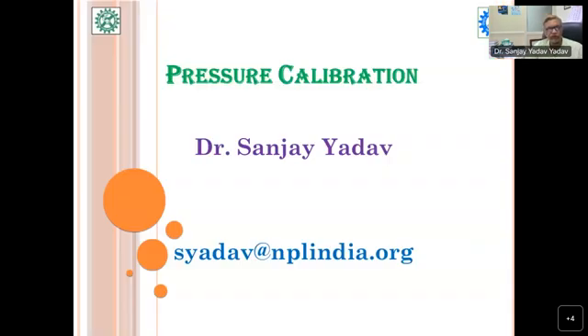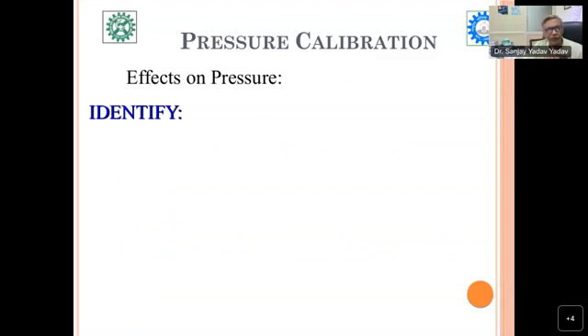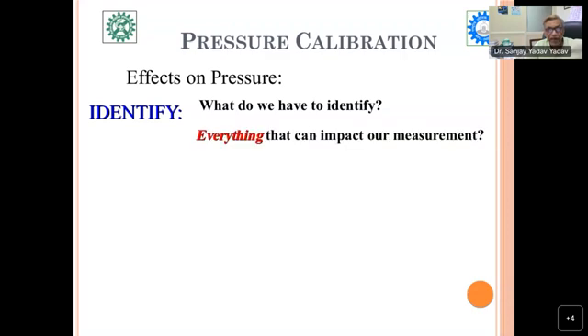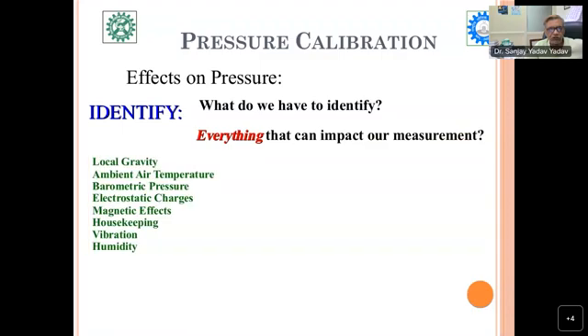So I will come now to this pressure calibration. When you are performing pressure calibration, you need to identify all the influencing quantities. What should we identify? Certainly, what affects the pressure measurement. Number one, everything that can impact our measurement. Those at the environmental condition level: local gravity, ambient air temperature in the room, barometric pressure, electrostatic charges, magnetic effect, housekeeping, vibration, and humidity prevailing in the room.